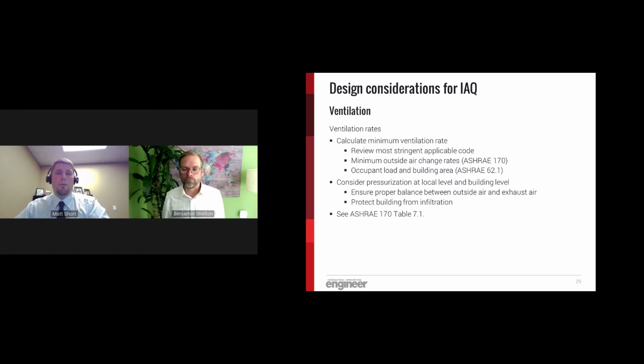Once the path of travel for fresh air is established, we can calculate the required amount of ventilation air for the building and for each individual piece of air handling equipment. Start by reviewing the applicable codes. Establish which codes or standards are the most stringent for each space to ensure the space is effectively ventilated. These ventilation rates can be described in CFM per square foot, CFM per occupant, or air changes per hour, depending on which code you're referencing.